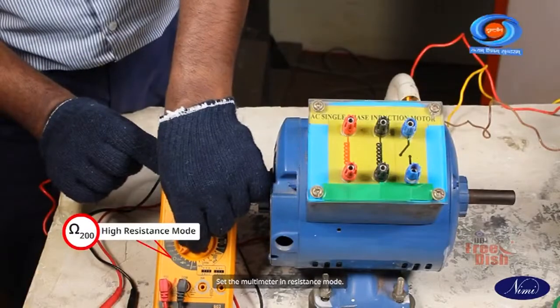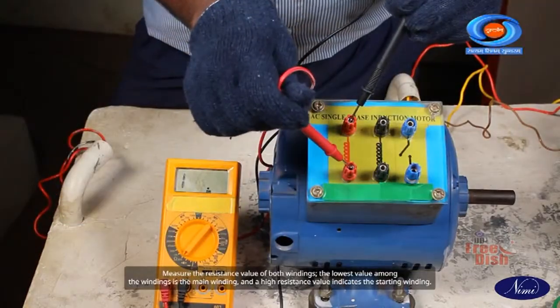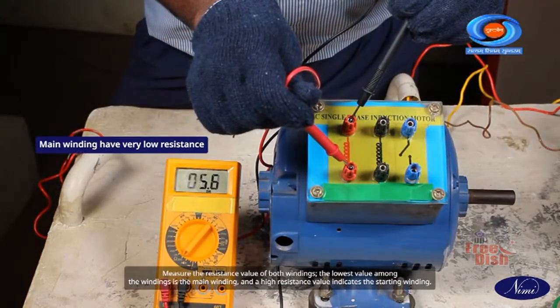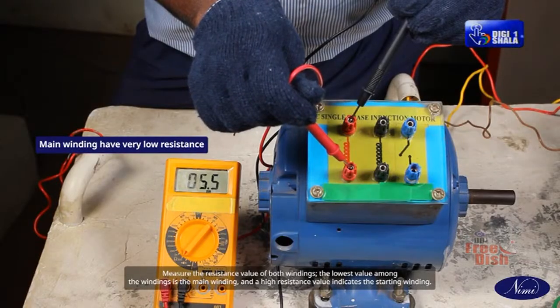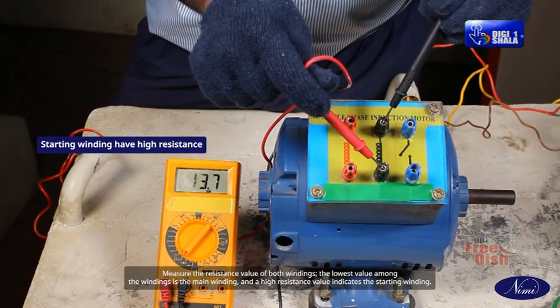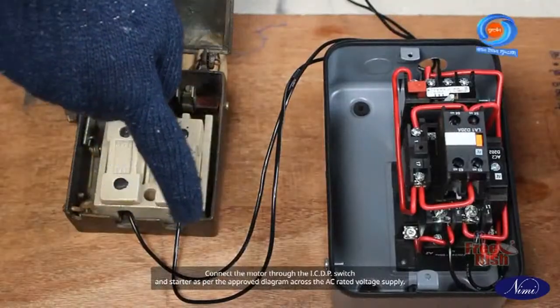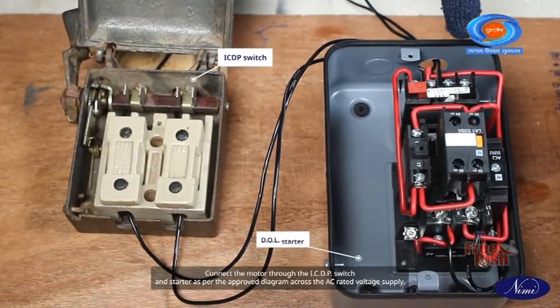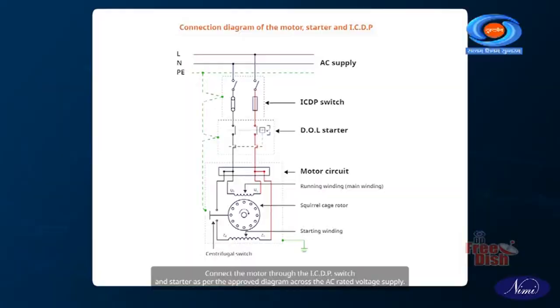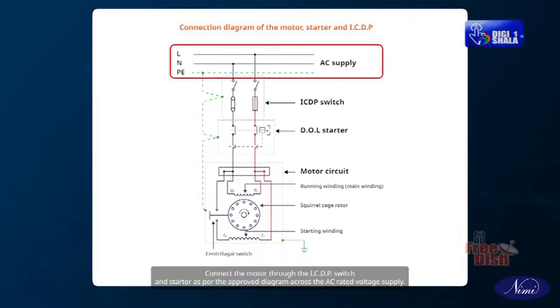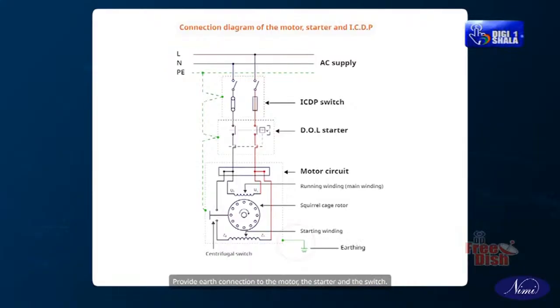Set the multimeter in resistance mode. Measure the resistance value of both windings. The lowest value among the windings is the main winding, and a high resistance value indicates the starting winding. Connect the motor through the ICDP switch and starter as per the approved diagram across the AC rated voltage supply. Provide earth connection to the motor, the starter and the switch.